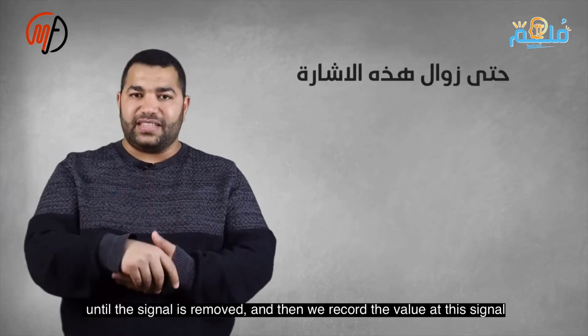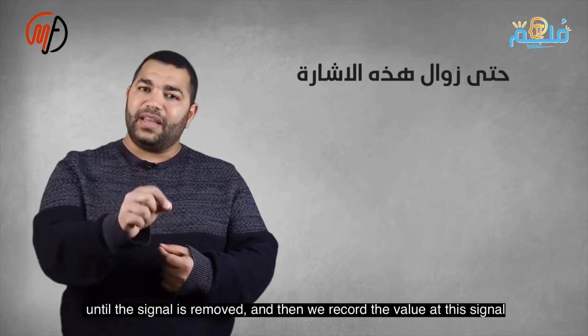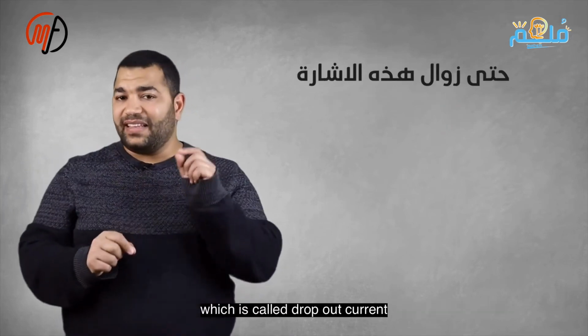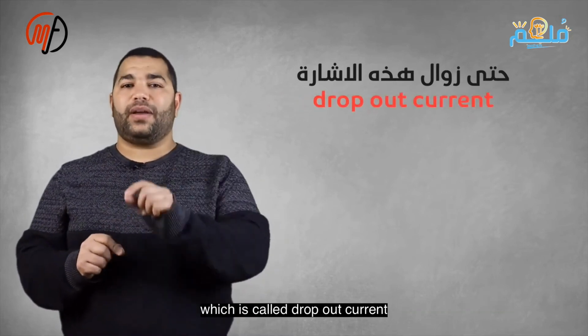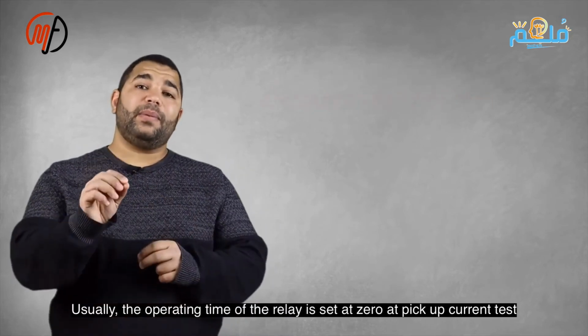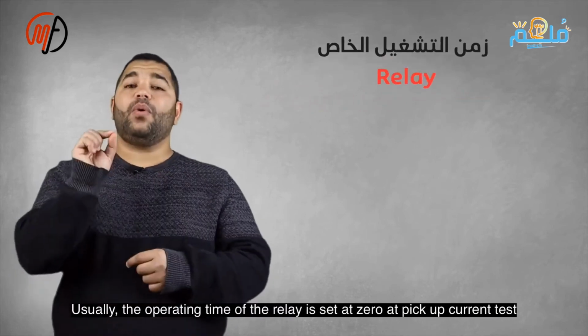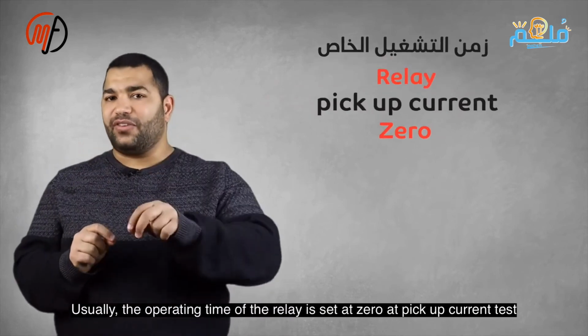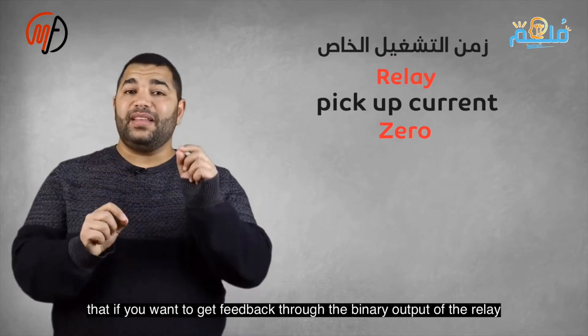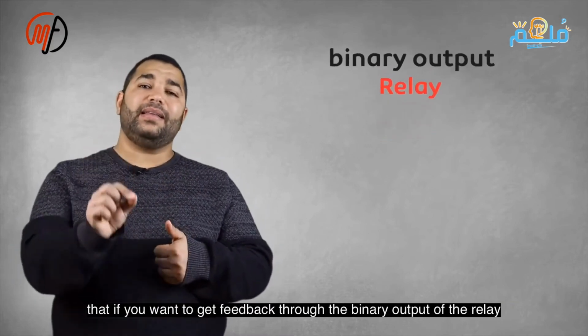The relay's operating time is set to 0 when testing the pickup current. The relay's output contact connects through a multimeter set to the buzzer function. If the contact closes, the multimeter buzzes, indicating a pickup current. We record this value, then decrease the current until the buzzer stops, recording that value. This measurement helps us calculate and understand its significance.